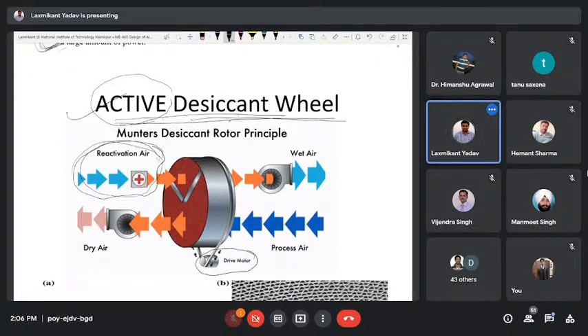Okay, so this is the cross section of the desiccant wheel. This is divided into two parts. One is called the reactivation section, this is the small section, and the larger section is called the adsorption section or process section, where dehumidification takes place. Here the process air or atmospheric air enters the desiccant wheel, and there will be dehumidification. So this dry air is warm air. There will be heating because of chemical dehumidification, because of heat of adsorption.